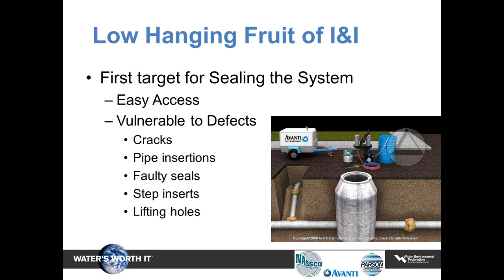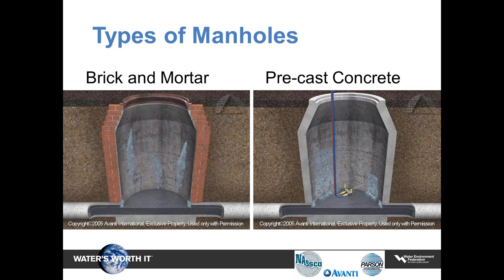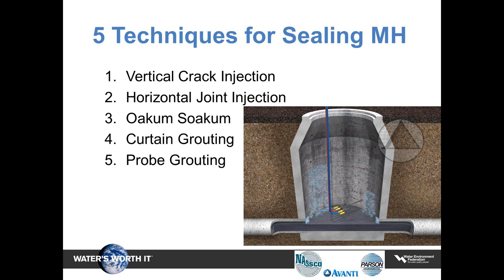Let's review a number of techniques for sealing leaking manholes: vertical crack injection, horizontal joint injection, oakum soakum, curtain grouting, and probe grouting. The following animations will help us understand what can be done to stop leaks in a manhole permanently. In the vertical crack injection animation, you see the leaking manhole with water coming in, and injection holes being drilled from typically the lowest point. You drill at a 45-degree angle toward the crack, a distance off the crack equal to about half the wall thickness, typically on either side of the crack.